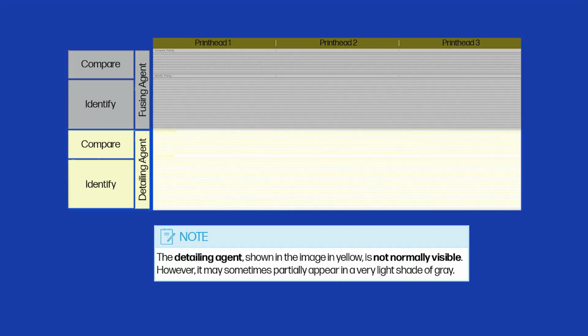Note that the detailing agent, shown in yellow in the image, is not normally visible. However, it may sometimes partially appear in a very light shade of gray. If visible, perform the detailing agent cleanliness diagnostic to analyze for cross-contamination, keeping in mind that this status plot can't guarantee proof of cross-contamination.